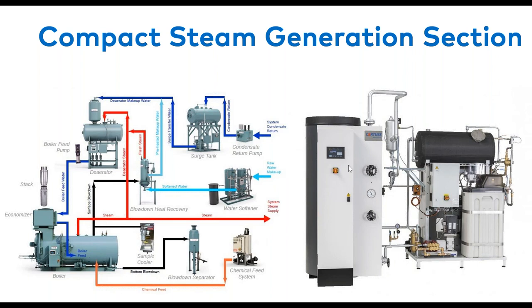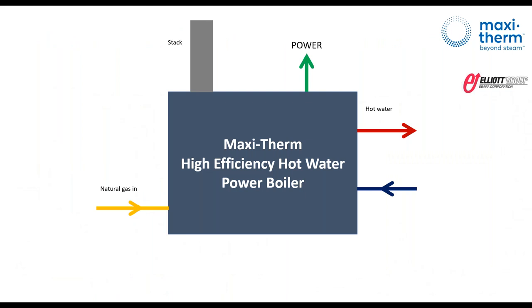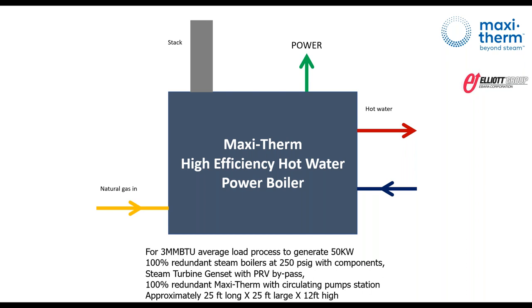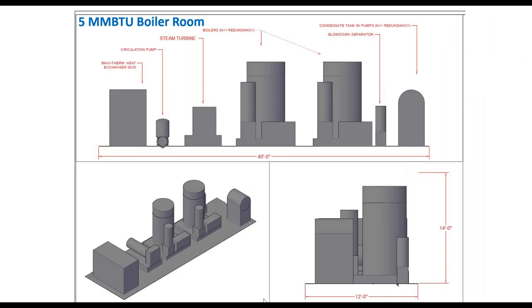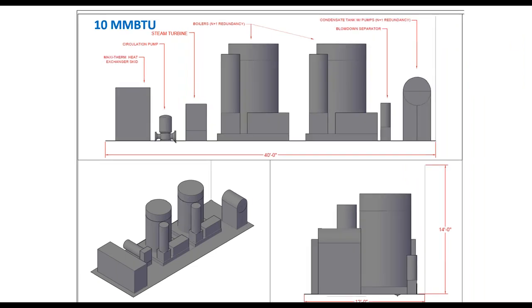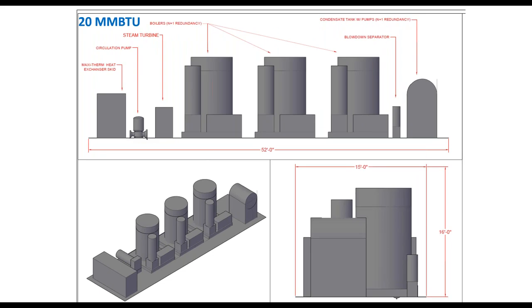The downside of that design is the water treatment. If you fail the water treatment, there's only one tube pass, so you plug the tube, right? In our case, if we do 100% closed loop, like a skid package can do, the water treatment is not a big thing. So let's say we use those coil type boilers to do a 3 million BTU unit to generate on average 50 kW, with 100% redundancy on the Maxi-Therm, 100% redundancy on the boiler, and one steam turbine with a PRV bypass if something goes wrong. Well, you need 25 by 25, and that's it. If we do a 5 million BTU unit, you'll need 500 square feet. 10 million BTU, another 500 square feet, and a 20 million BTU will need more, around 800 square feet.